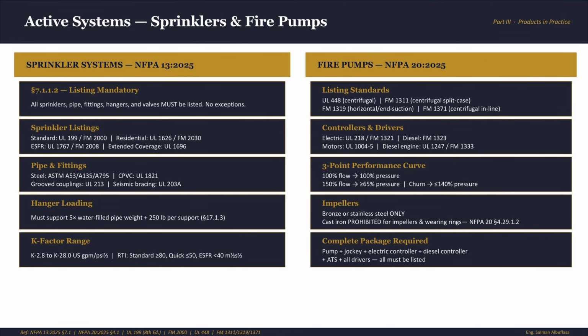Although the jockey pump itself is not required to be listed under NFPA 20. Why? Because the jockey pump is a pressure maintenance device that holds the system pressure during minor leaks and prevents the main pump from starting unnecessarily. So if the jockey pump fails, the main pump starts and takes over. But the controller for the jockey pump must be listed. And this basically should cover what the code requires from the pump, how it's built, what's listed, and what's permitted.